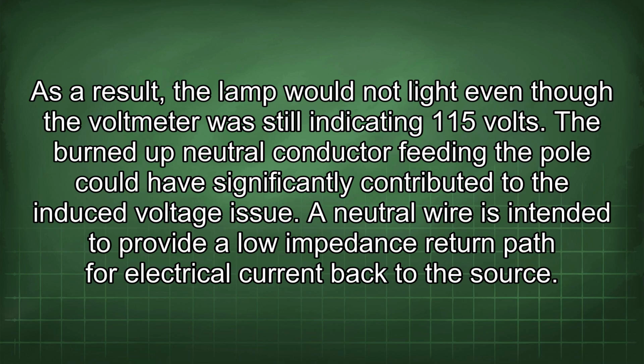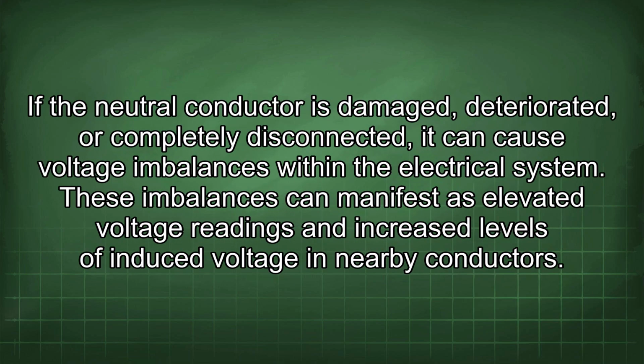The burned-up neutral conductor feeding the pole could have significantly contributed to the induced voltage issue. A neutral wire is intended to provide a low-impedance return path for electrical current back to the source. If the neutral conductor is damaged, deteriorated, or completely disconnected, it can cause voltage imbalances within the electrical system. These imbalances can manifest as elevated voltage readings and increased levels of induced voltage in nearby conductors.